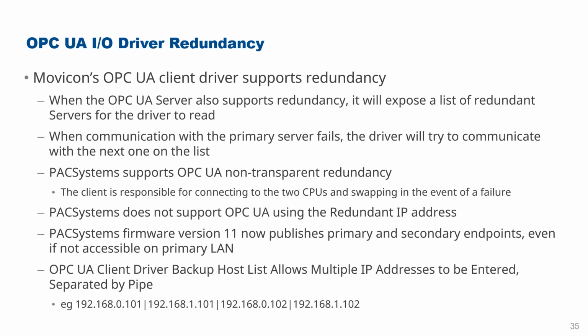But the challenge with those is, they often give you a master and a backup PLC, but they might not handle the network redundancy. So again, that's when you're into RSTP or something, but RSTP might not be fast enough on the control network. So at least with PAC Systems and using OPC-UA, we've now got full support for this redundancy operation.